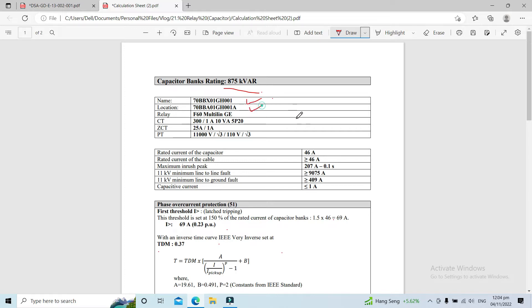We are using the relay from GE, which is the F60 multi-lin. The current transformer is rated at a ratio of 300:1 ampere, 10 VA burden, class 5P20. Our zero-sequence current transformer is 25:1 ampere, and our PT rating is 11,000 volts to 110 volts.